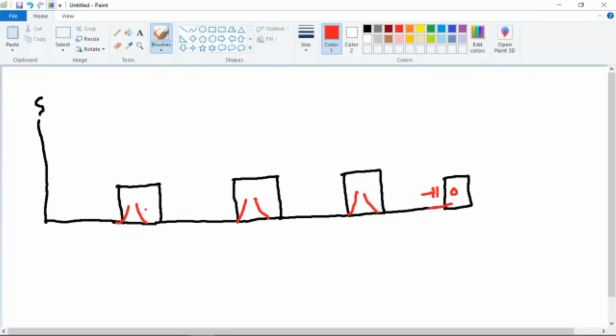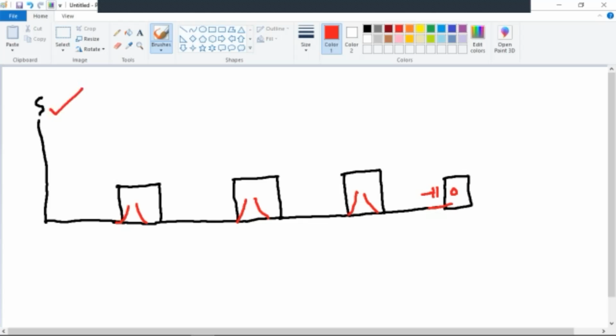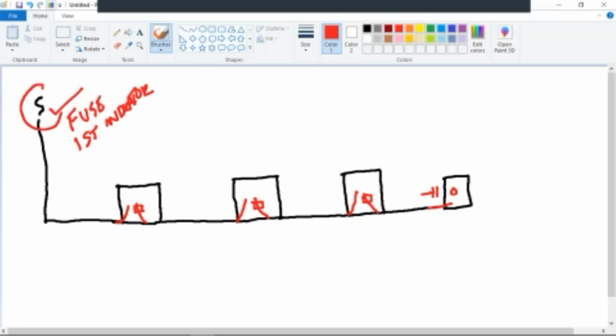All right, typically what we'd like to do, especially if we were coming off a fuse right here, is we would put our fault indicator on this cable. That's the outbound on every single transformer. Okay. The fuse, now remember this, the fuse is your first indicator. It's a fault indicator in itself. If you have a blown fuse, that is your first fault indicator. So it lets you know right away, I need to isolate the first span and test the first span.